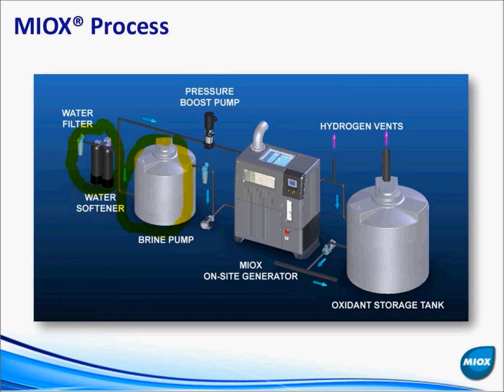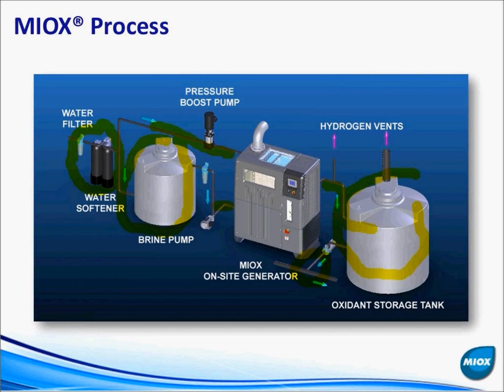Part of the stream goes into a brine tank where we make up a saturated brine, and part goes into the back of the generator. The generator automatically combines and blends those two streams at the right ratio, controls the electrolytic process, and produces an oxidant that goes into the oxidant tank downstream. That oxidant is then dosed into your application — for drinking water, for example, one pump may handle pre-treatment before a filter and another for final disinfection.